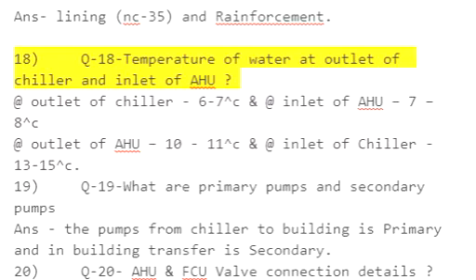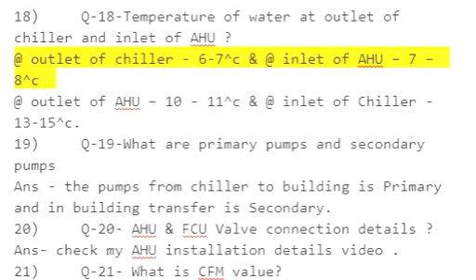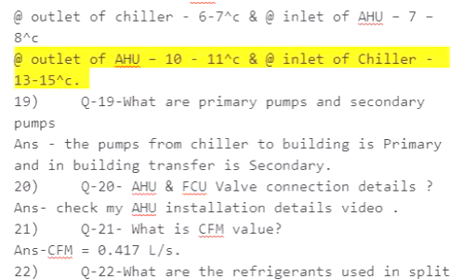Q18: Temperature of water at outlet of chiller and inlet of AHU — at outlet of chiller: 6 to 7°C. At inlet of AHU: 7 to 8°C. At outlet of AHU: 10 to 11°C. At inlet of chiller: 13 to 15°C.